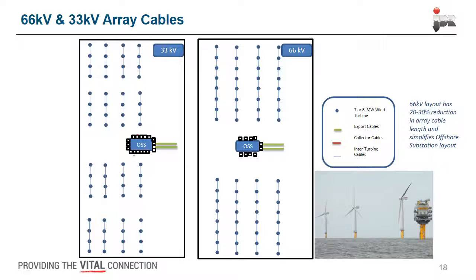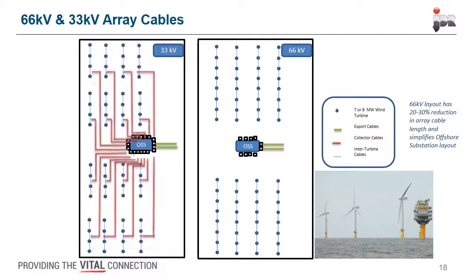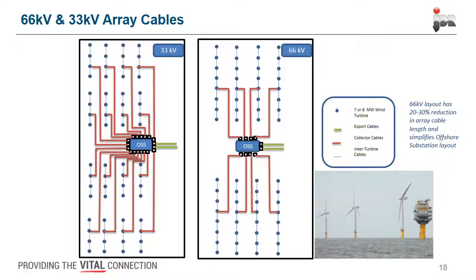So if I now add in the cables that go back to the offshore substation, what we see is that the 33 kV requires a large volume of cables going into the offshore substation, and 66 kV half that amount of cables. So the overall effect of this is that typically the reduction in cable length required is between 20 and 30%. And of course, that's 20 or 30% cable you're not having to make, but it's also 20 or 30% less that you have to install, and the offshore substation becomes a much simpler structure. So this is what's driven the move from 33 kV to 66 kV as part of cost reduction, and it fits with the bigger turbines that are coming on stream now.